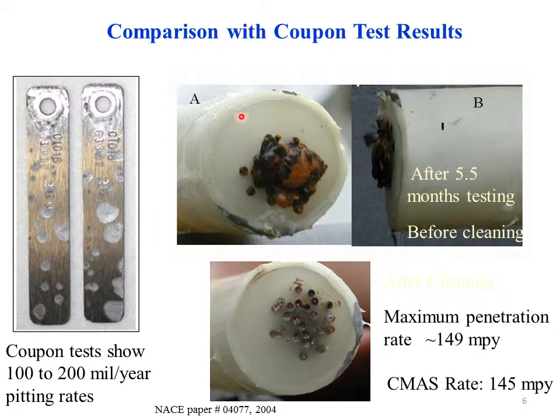In this slide, we compare a CMAS probe after 5.5 months of testing to a coupon inserted into the same environment. After cleaning the corrosion product from the CMAS probe, as seen in this image here, the maximum penetration rate was measured to be 149 mil per year. From the coupon tests, the maximum penetration rate was calculated to be between 100 to 200 mils per year. The 149 mils per year calculated from the CMAS probes correlate with the coupon tests that show 100 to 200 mil per year corrosion rates. This is referenced from NACE paper number 04077, published in 2004.